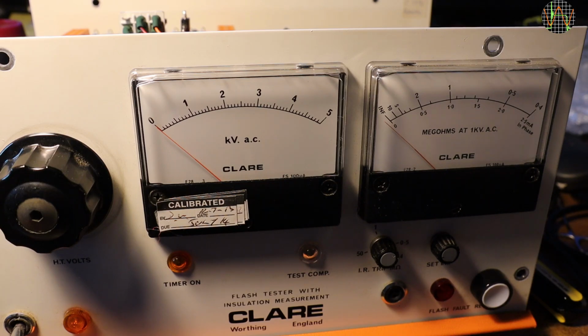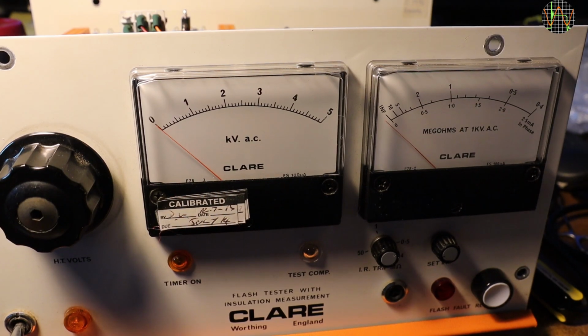milliamps. The later models of the 203 testers apparently can go up to 125 milliamps and have a flash trip bypass burnout button to, as the manual says, observe arcing in the item under test. My unit doesn't allow that. Maybe it could be modified, but I will leave that for another day.